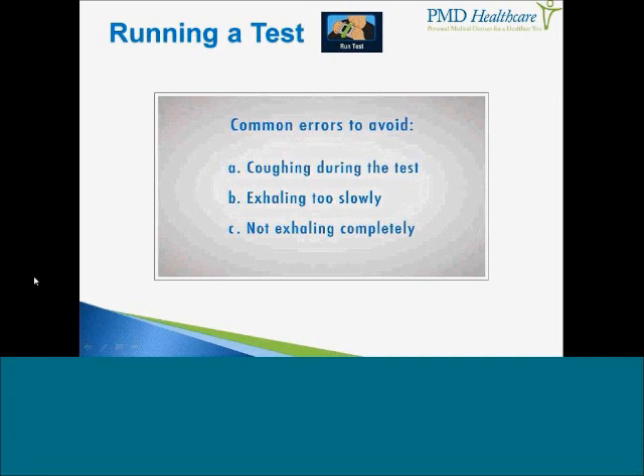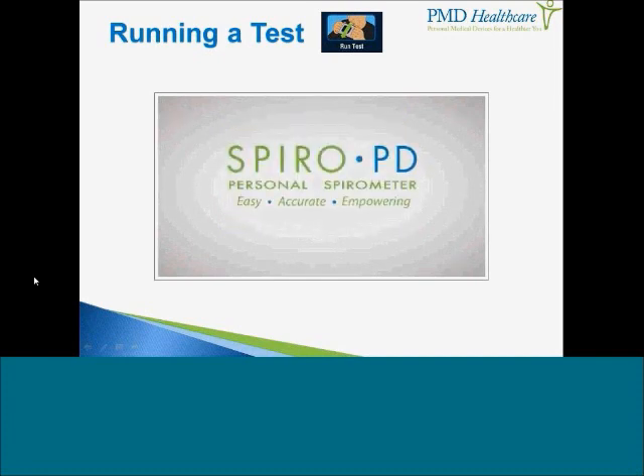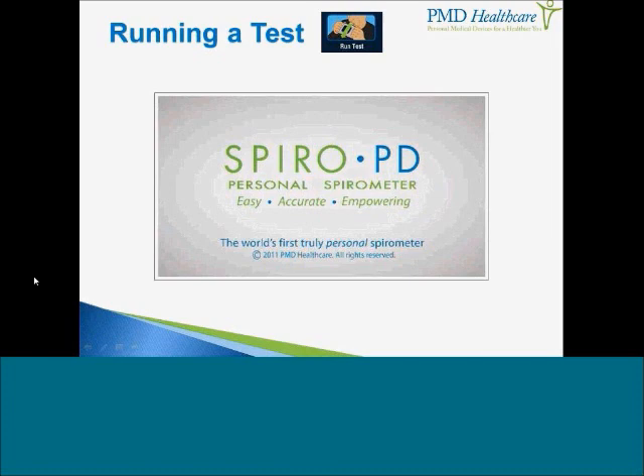Here are common errors to avoid: coughing during the test, exhaling too slowly, and not exhaling completely. A couple of additional tips: it's really important when performing the test to make sure you sit up nice and straight and tall. Make sure that you do your breathing test in the same position every single time — whether that's sitting down or standing up. Keep your chin up and try not to hunch over as you're breathing. Also remove any gum or objects you have in your mouth, and that will make sure you do the test accurately every time.